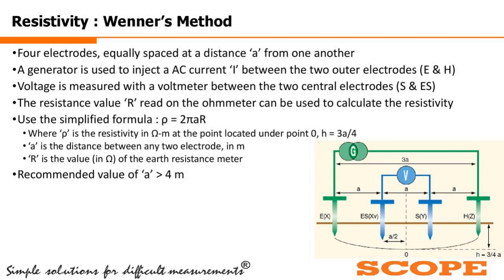We can then use the formula rho equals 2 pi A into R to calculate the resistivity, where rho is the resistivity in ohm meter at the point located under point 0. So it is resistivity with respect to which position, that we should know. The position is 0. As you can see, the 0 is placed just above the letter C of the scope logo, which is lying at a distance h from the surface of the earth.